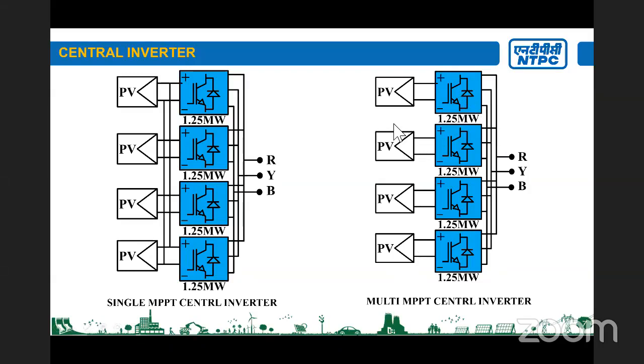Each converter will operate the PV connected at its terminal at a different MPPT voltage level. But in this case also, it is not a very true kind of MPPT. The MPPT range among the converters is limited to say 50 volts. Say PV1 has some operating voltage and the other PV has some other voltage, but the voltage difference will again be limited to around 50 volts. In this configuration, there are two difficulties again. One is circulating current among the converters at the AC side, and from the PV side also there will be some circulating current. That circulating current is the reason for limiting the PV array to not operate over a wide range of voltage. That cap of 50-60 volts is there so that the circulating current is limited.